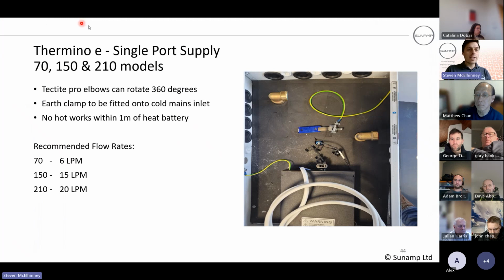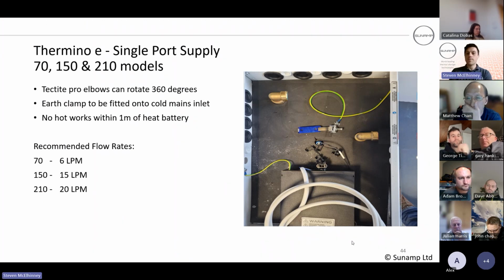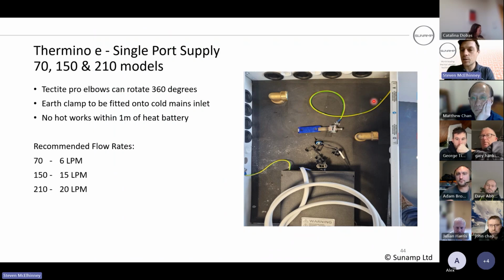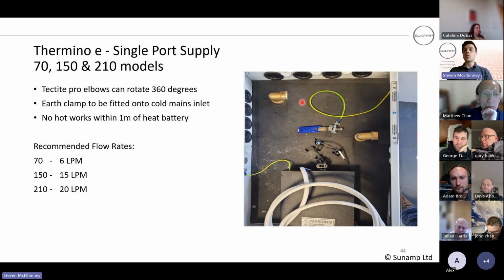So yeah, mechanical connections. So we've got a little bit of flow rates here as well. I think it was you, Adam, who asked about the earth clamp. That's the earth clamp there. So that just ties onto the side of the casing. Much clearer. Yeah, perfect. So you've got Tectite elbows in here. So they're fully rotatable. You can have a left or a right or a rear exit. This is just for the Thermino E 70, 150 and 210 models. So that's what we call a single port, one pipe in, one pipe out.